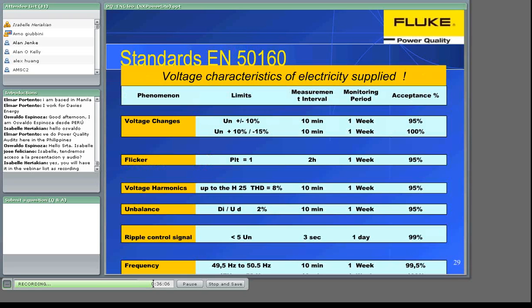This table displays the parts that characterize the product electricity and the corresponding limit values according to the standard 50160. Anyway, for the sake of honesty, we have to say that those limit values may change or may be applied in a different way from country to country. For instance, Denmark and France do not consider the 95% of the time, they only consider the 100%. Or a voltage change plus minus 10%. In Spain, plus minus 7% is applied. You see, those limit values can change from country to country.